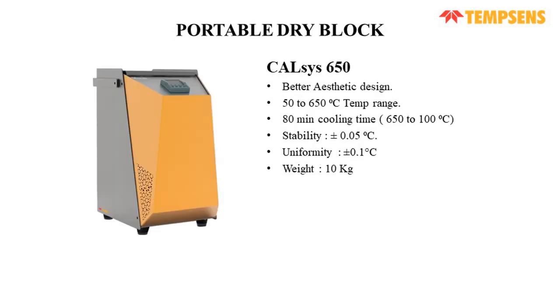Next I have CALsys 650. It is a very lightweight model, and the temperature range is 50 to 650 degrees centigrade. The cooling time is 80 minutes, and it cools down to 100 degrees in just 80 minutes from 650 degrees centigrade. The stability is plus minus 0.05 degrees centigrade, and the uniformity is plus minus 0.1 degrees centigrade.